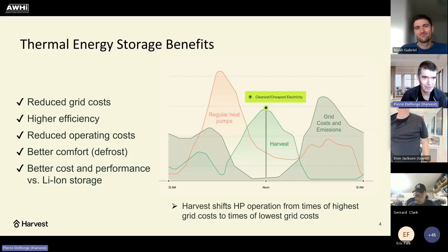The round trip efficiency of the thermal battery in Harvest system is about 95% compared to about 90% for an electrochemical battery when new, and for an electrochemical battery, both efficiency and capacity will degrade over time, whereas a thermal battery does not degrade over time, right? So I think electrochemical batteries are great for electrical loads, and thermal batteries are better for thermal loads. And that's kind of the message and the concept that is driving the Harvest Thermal company.